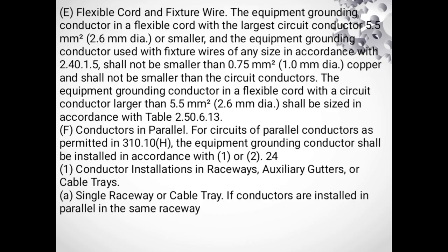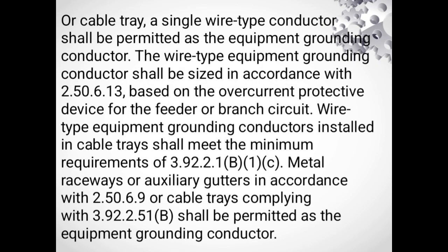F. Conductors in parallel. For circuits of parallel conductors as permitted in 310.10(H), the equipment grounding conductor shall be installed in accordance with 1 or 2. 1. Conductors installed in raceways, auxiliary gutters or cable trays. A. Single raceway or cable tray. If conductors are installed in parallel in the same raceway or cable tray, a single wire type conductor shall be permitted as the equipment grounding conductor. The wire type equipment grounding conductor shall be sized in accordance with 2.50.6.13 based on the overcurrent protective device for the feeder or branch circuit.